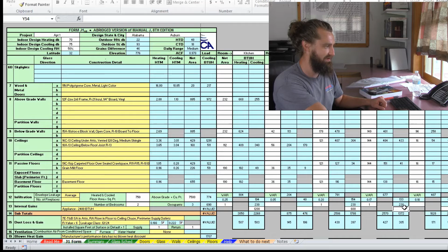So I'm not going to put all of this appliance load into the kitchen. I'll divvy it out between the bedrooms too. I'll put 1200 BTU in the kitchen, give bedroom 1 600, and the master bedroom 600, giving us an overall appliance cooling load of 2400 BTU. Now we're accounting for each of those in the bedrooms.